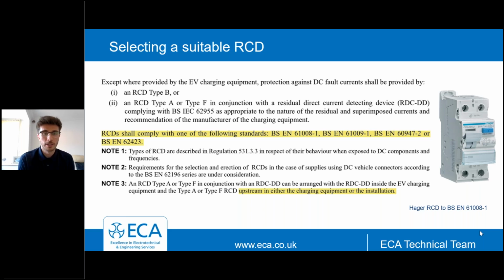So it may be that you need to put it within the installation itself. So it may be that you elect to put it within the consumer unit at the origin of the circuit. But just to provide a bit of clarity on that, the requirements of this regulation that are referred to on the previous slide is to protect the charging point. It doesn't necessarily have to be at the origin of the circuit, unless, of course, your installation method, maybe you've buried a PVC cable in the wall, for instance, your installation method may have specified it because of other requirements earlier on in BS 7671.